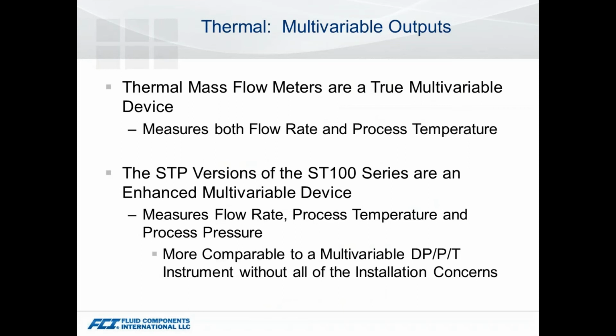The other thing to look at is that thermal is truly a multivariable device. With all of our meters, you're getting both flow rate as well as process temperature being measured. The devices have 2 analog outputs, so you can bring both of those process parameters across. In the case of an STP version, where we had that pressure transducer, you actually have 3 analog outputs on that model, so you can bring all of that across. This gives us the capability of matching up truly to a multivariable pressure transmitter, or the configuration of a differential pressure transmitter with pressure and temperature compensation.